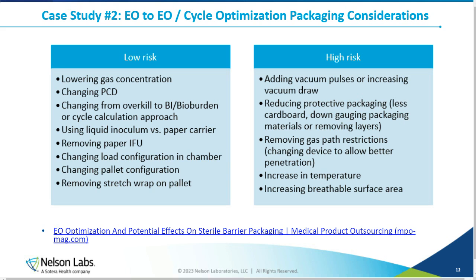If you're lowering the gas concentration, that's really going to have less of an effect because you have less of that nasty gas to deal with. If you're going to change your PCD, that means that you're going to have a shorter cycle. That's not really going to mean you have to repeat a packaging validation. Same thing if you're going to change from the overkill to a BI bioburden or a cycle calculation, as well as if you're going to change from the paper carrier to the liquid inoculum, because again, that's just going to shorten your cycle. If you want to remove your paper IFUs because cellulose materials absorb EO, or you want to change your load configuration in the chamber to change how you've put things on the pallet or how you're loading it in there to make it so that there's more pathways for gas to get into the center of the load. Or if you're going to pull the stretch wrap off and change it to banding so that you are, again, removing a barrier, none of these things are going to impact your packaging per se. So these are all things that you could easily justify in your change control just using a paper justification.